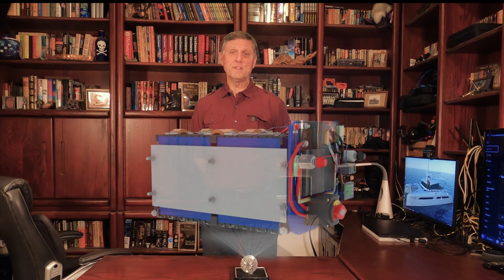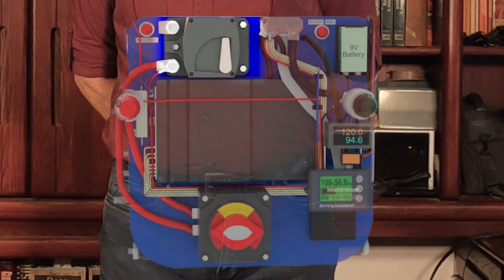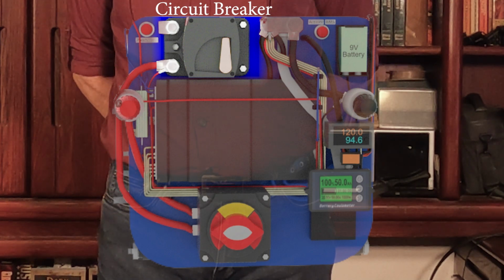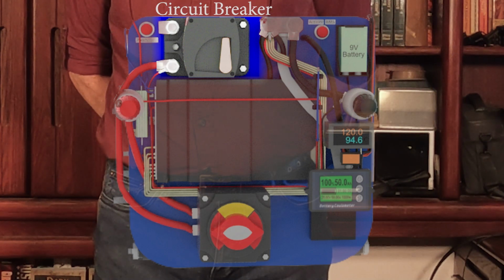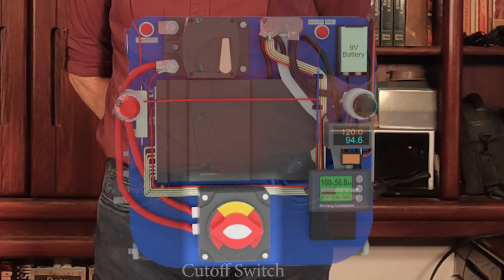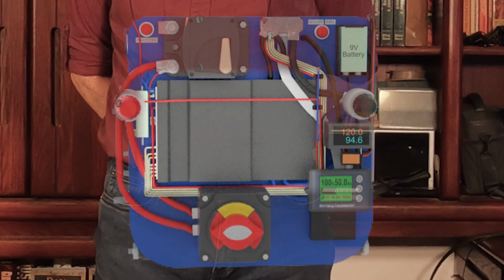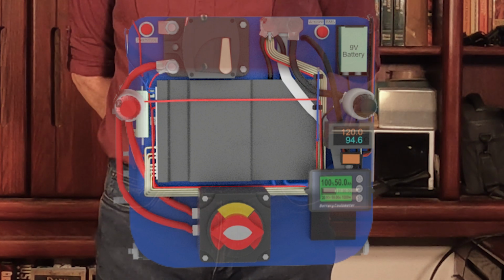I'll spin the battery around and stop at that HDPE panel. Here you can see where we mounted the internal 200 amp circuit breaker. This can also be used as a switch to cut off the batteries from the external terminals. Next, down below, here is the external cutoff switch, which allows us to turn off this battery without opening the case. Now we get to the heart of the control systems.